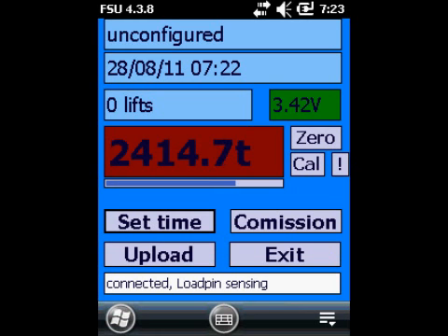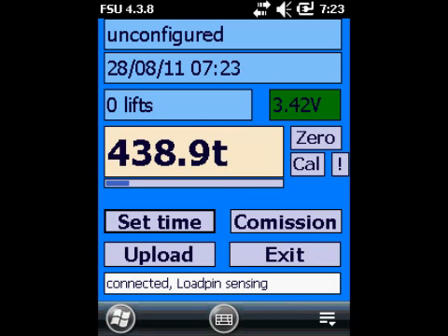It's important to make sure that that bar moves up when you lift a load, and you can see here I'm lifting a load. See the bar moves to the right, and that it moves down again when you take the load off. It's also important that the bar doesn't move past or up to the very end when you lift less than a full load, because otherwise it'll cause that signal to clip later on. If it doesn't move this far, then you should check your wiring on your load cell.